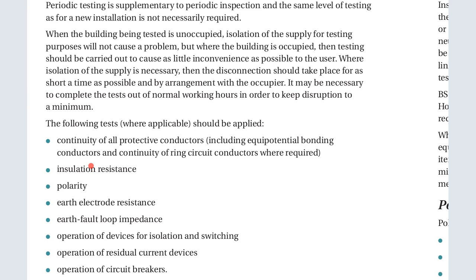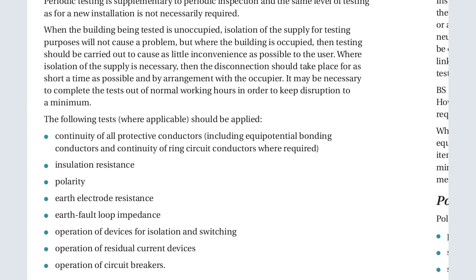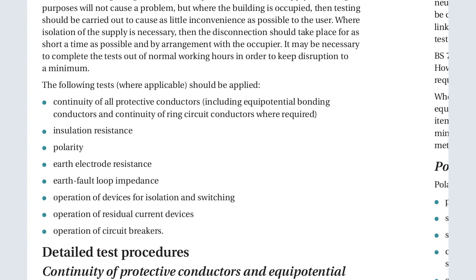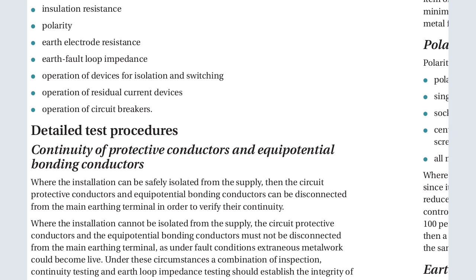Remember that the periodic test is done for a building that has already been occupied and had already undergone the initial inspection and testing when it was being built. So it may be necessary to complete the tests outside of normal working hours in order to keep disruption to a minimum. The following tests, where applicable, should be applied. The continuity of all protective conductors, including the equipotential bonding conductors, and continuity of the ring circuit conductors where required. Then we have insulation resistance, polarity, earth electrode resistance, earth fault loop impedance, operation of devices for isolation and switching. We also check the operation of the residual current devices.